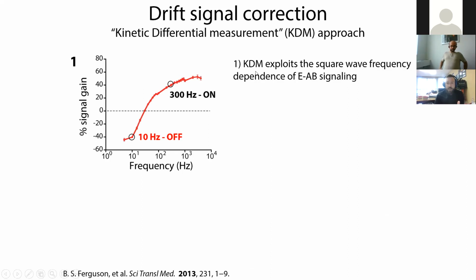The first assumption is based on KDM exploiting the square wave frequency dependence of E-AB signaling. This means, as I told you in the first slide, that by changing the square wave frequency, we can change the signal behavior of our sensor. Why? Because changing the square wave frequency changes the rate of sampling of the electrochemical signal. So using a low square wave frequency, we are collecting the signal more from the unbound state, which displays lower electron transfer kinetics. For this reason, here we observe a signal off, because this represents the reduction in the population of the aptamer from not bound state to bound state.